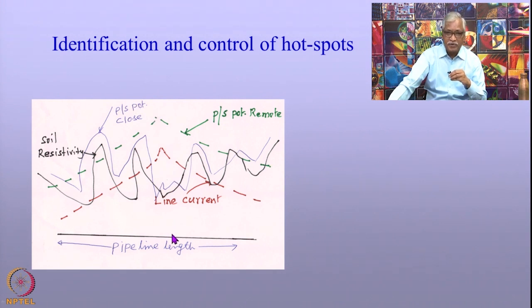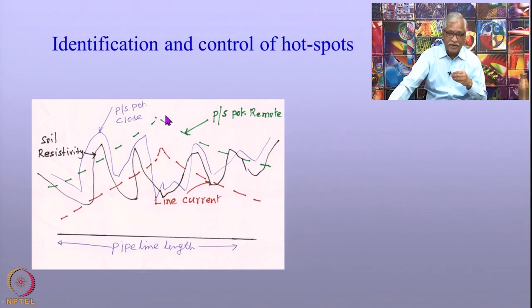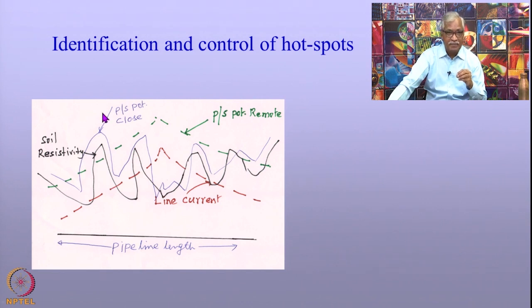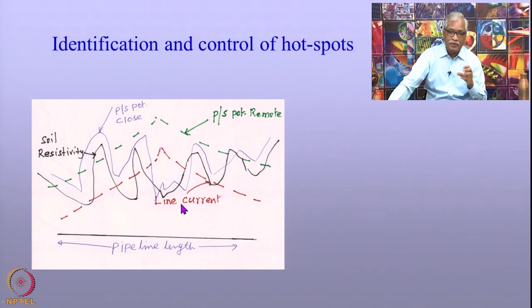Overall, at a particular location the pipe-to-soil potential remote is relatively positive, and we also see that at this location the current leaves the pipeline — it is higher here. So this location corresponds to the anode, meaning the pipeline at this location will experience more severe corrosion relative to the remaining segment. It is therefore possible to identify hot-spots using all four parameters: pipe-to-soil potential remote, pipe-to-soil potential close, soil resistivity, and line current measurements.